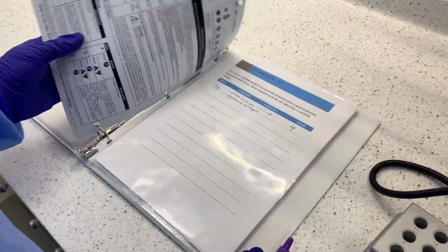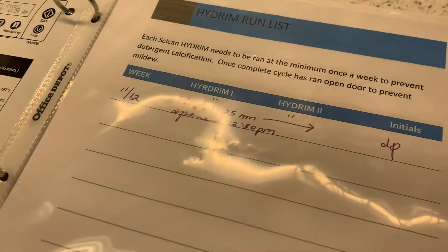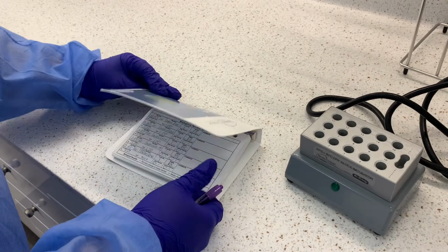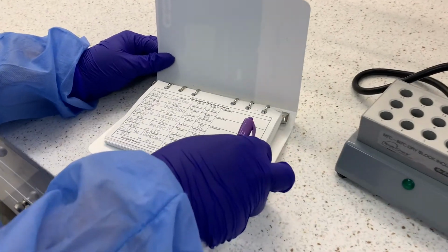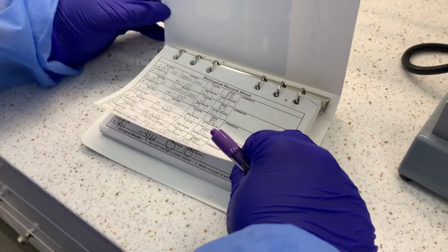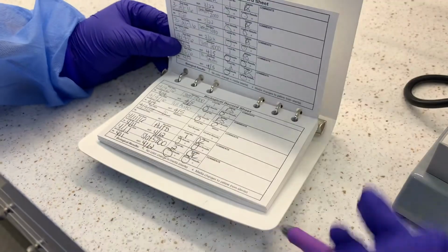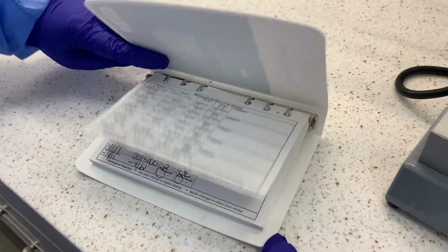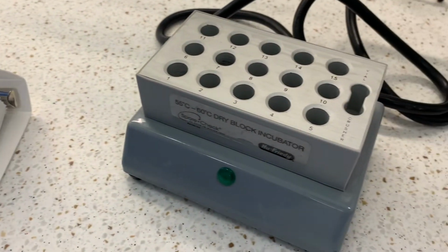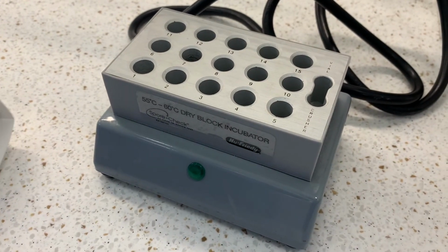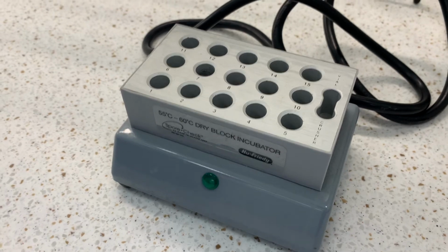All sterilization use must be recorded, processing and results. Biological monitoring must be done once a week. To perform, label capsules and place them in the autoclave with instruments. After it has run, it is crushed and results are recorded after sitting for 8 hours. If the vial changes color, then the autoclave is not working correctly and cannot be used until it has been maintenanced.